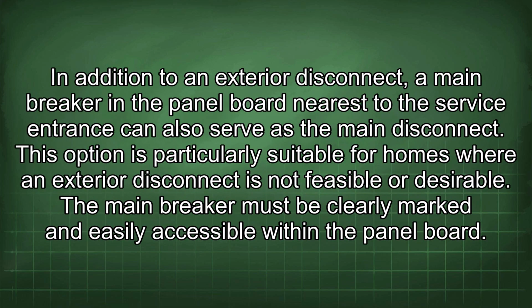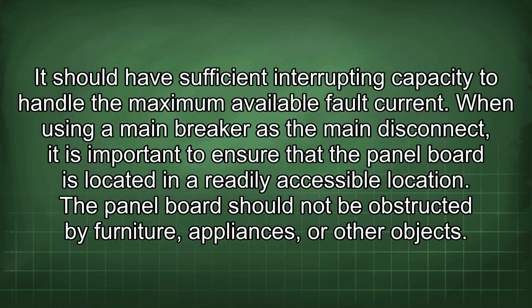In addition to an exterior disconnect, a main breaker in the panel board nearest to the service entrance can also serve as the main disconnect. This option is particularly suitable for homes where an exterior disconnect is not feasible or desirable. The main breaker must be clearly marked and easily accessible within the panel board. It should have sufficient interrupting capacity to handle the maximum available fault current.